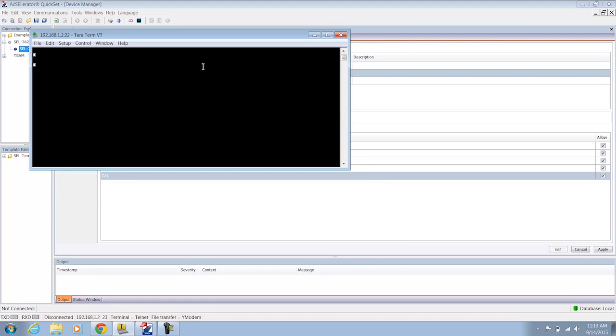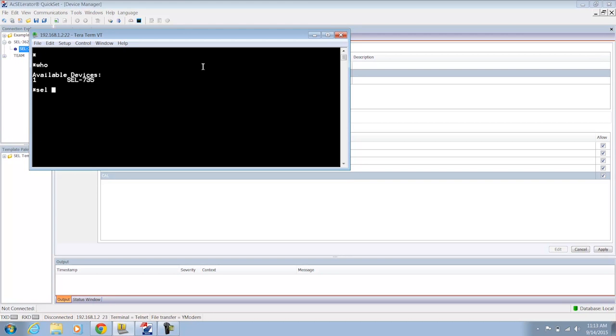Now at this point in time I want to be able to view the list of devices that I have access to as a member of the Supervisor's group. So I'm going to type the WHO command, and that's going to show the 735 relay that I have access to as a member of the Supervisor's group. To select and access the prompt of that relay, I can type in the command SEL, which is SELECT, and then 1, which is the current device, the 735 relay. And now you can see that I have access to the prompt on this relay.